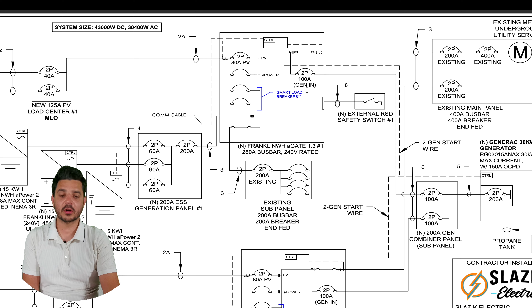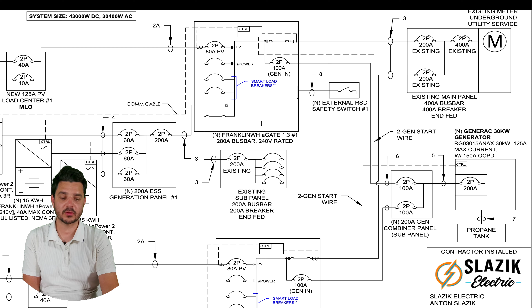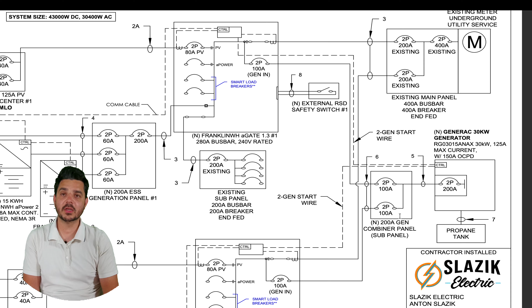Here is our external rapid shutdown device, as we're indicating on here. Here's that 2-pole 100 amp generator breaker. That's going to be in the aGate. That's what this is. This is the automatic transfer switch. And that's that sub panel from the generator, 30 kilowatts. It's 125 max current with a 150 amp overcurrent protection device. Now it's going into a 200 amp sub panel, and then it's splitting across these 2 units, each at 100 amps.